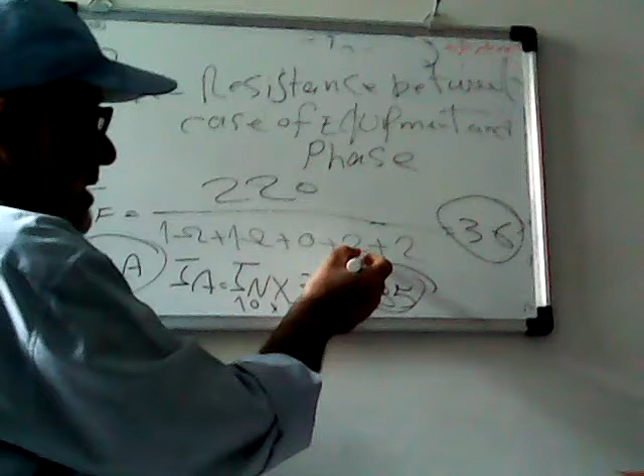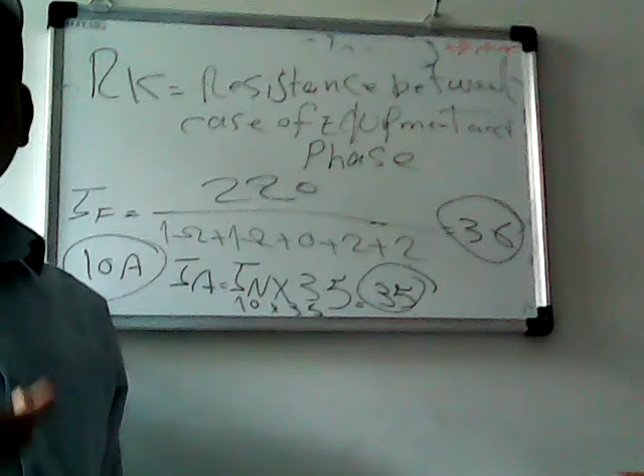In here we see there are fuses of 10 ampere. With this condition of our circuit, after the short circuit between phase and case of body, the fuses will immediately be cut, because this is 36, and the fuse rating is 35. Immediately it's cut, and this is our favorite and what we want.